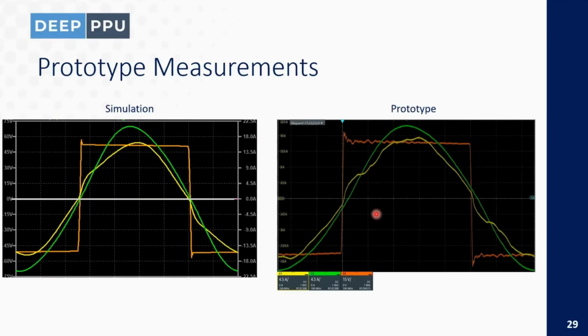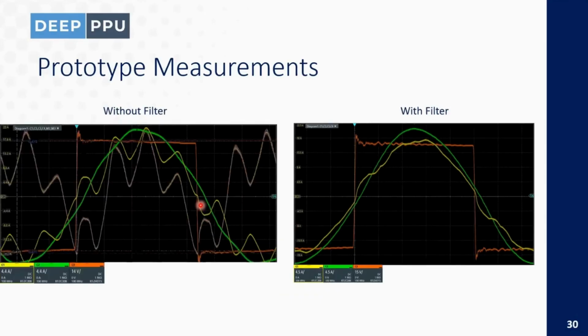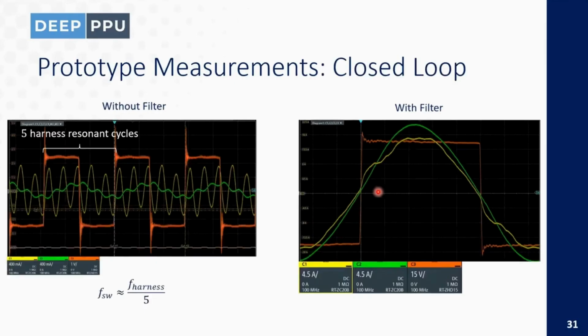The filter works well. We were able to go from the case on the left with these really high frequency harmonics to the case on the right. More importantly, we are now able to close the loop correctly. Before, the high frequency harmonics were affecting the closed loop; now the control correctly switches at the frequency of the load.